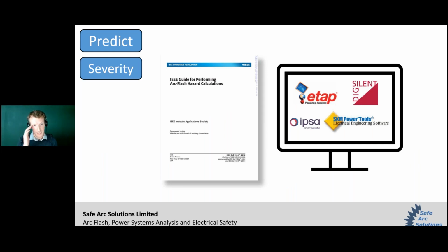Severity is most accurately determined these days by getting an arc flash study undertaken. In simple terms, this means taking a computer model of your network and completing calculations, based on an internationally recognized standard, to calculate the thermal energy released by an arc. There are other effects of the arc, but thermal energy is the one that really takes precedence.